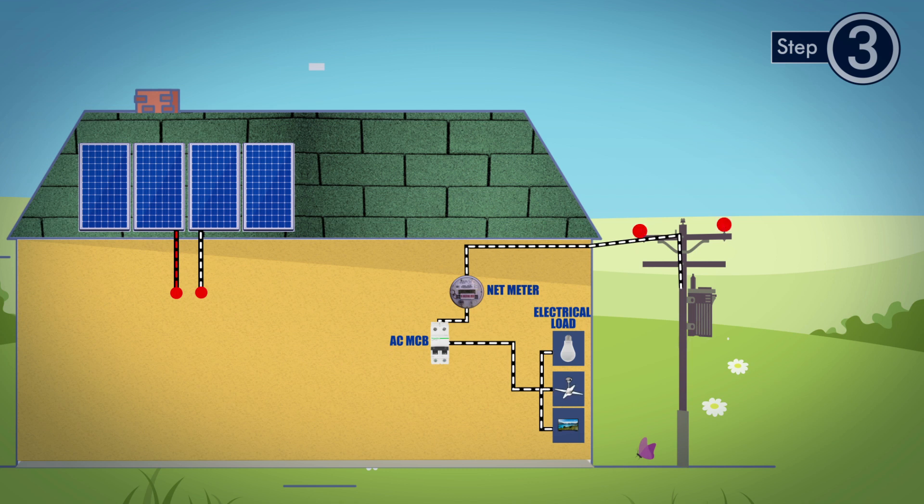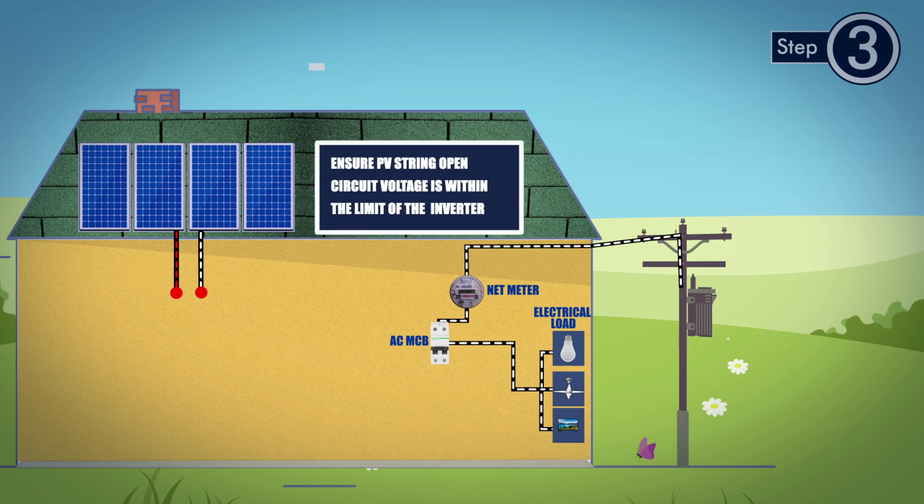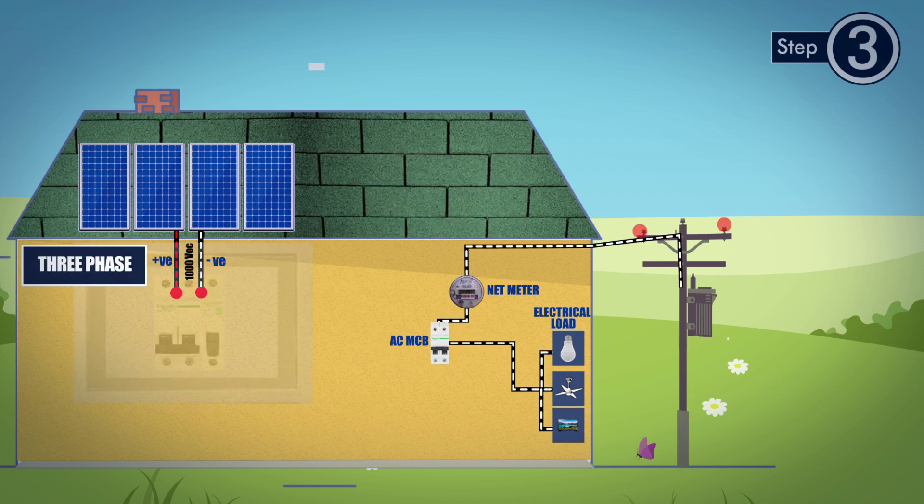Before connecting inverter, please make sure the PV string open circuit voltage is within the limit of the inverter. That is, maximum 600V open circuit for single phase inverters, maximum 1000V open circuit for three phase inverters.